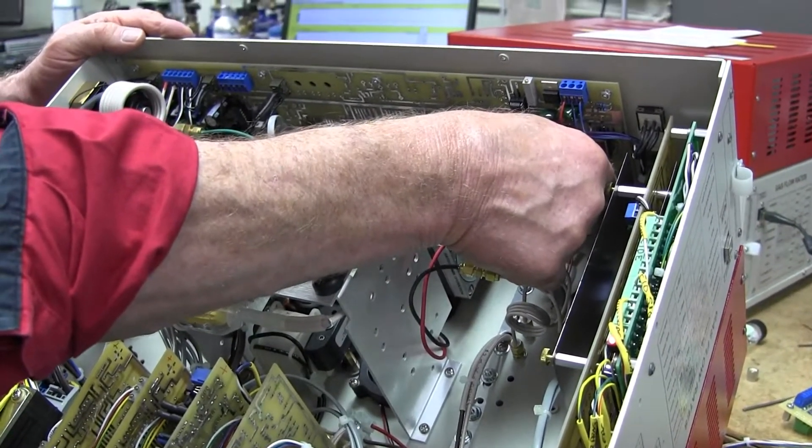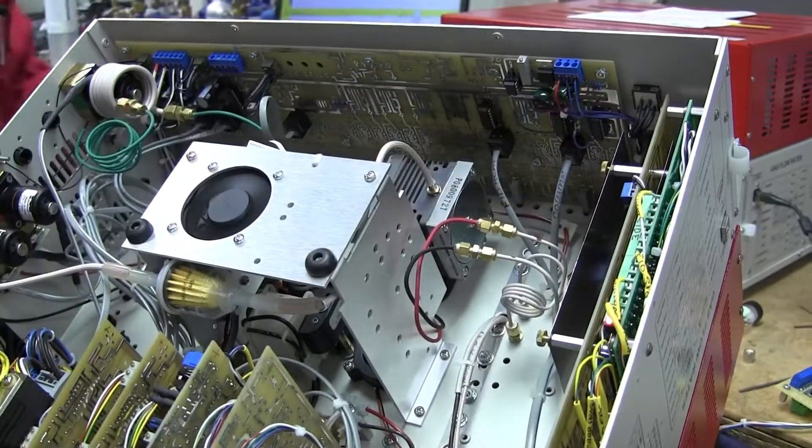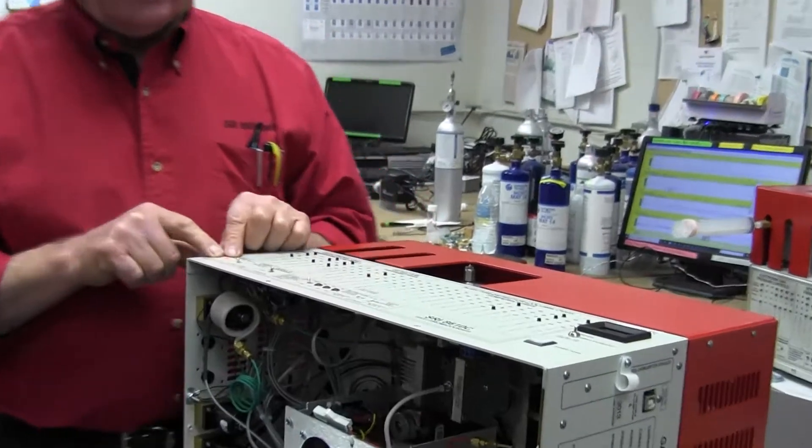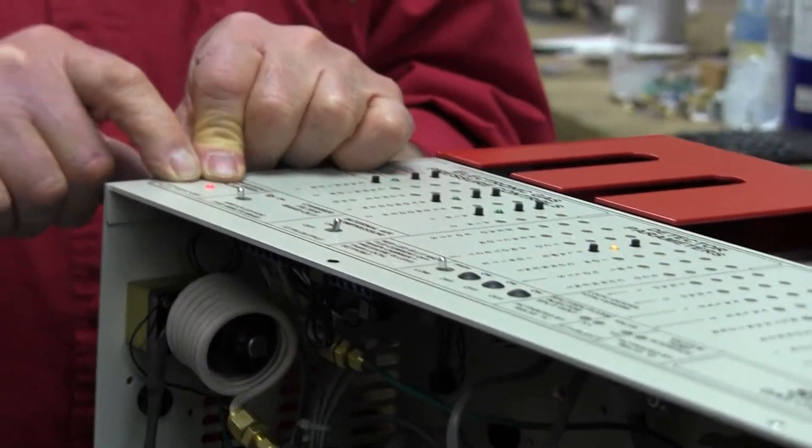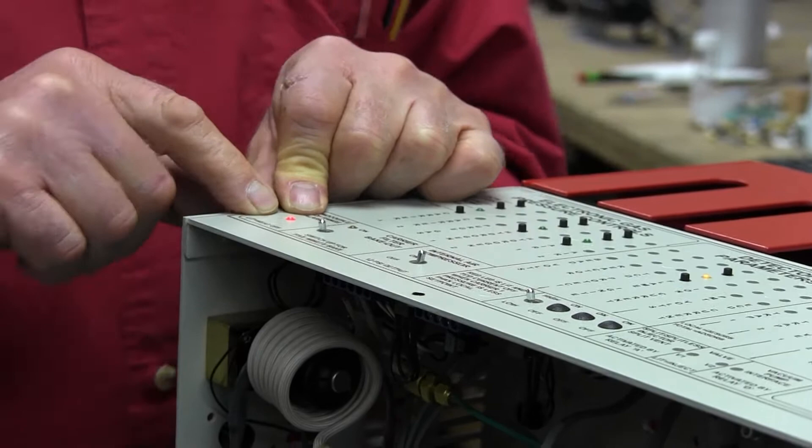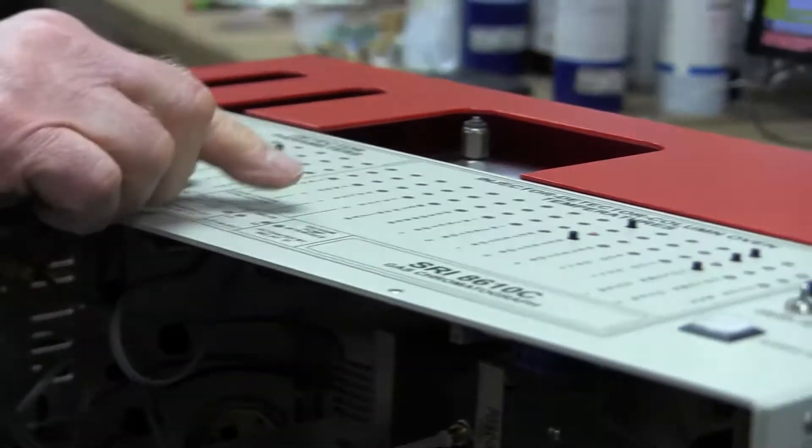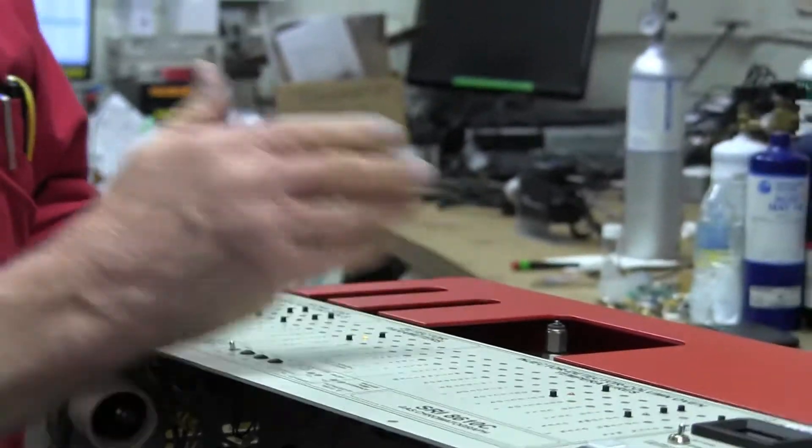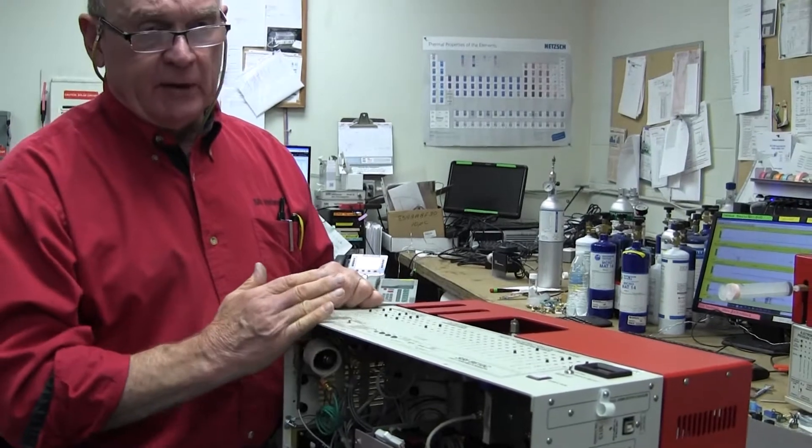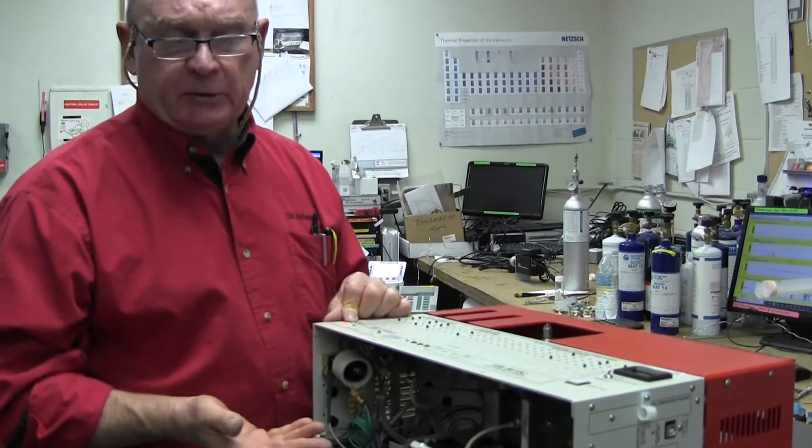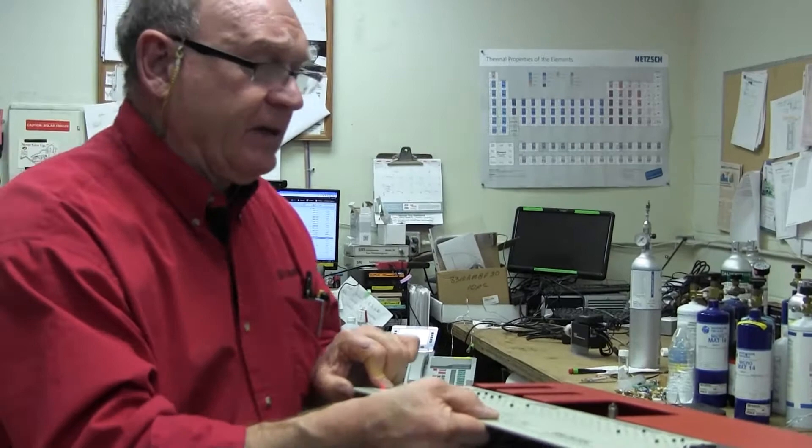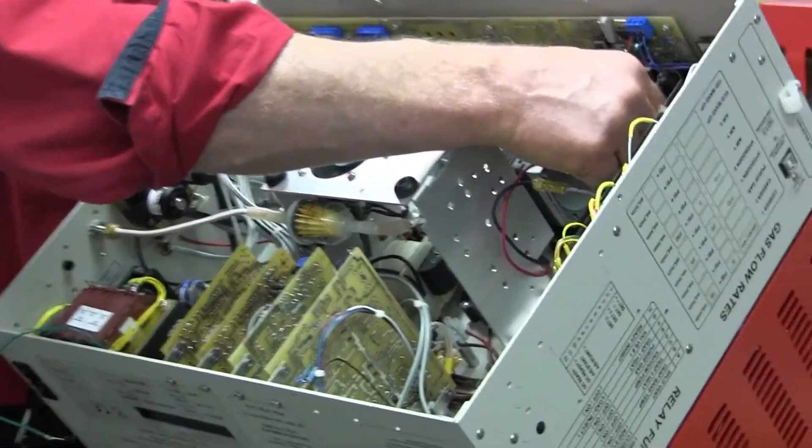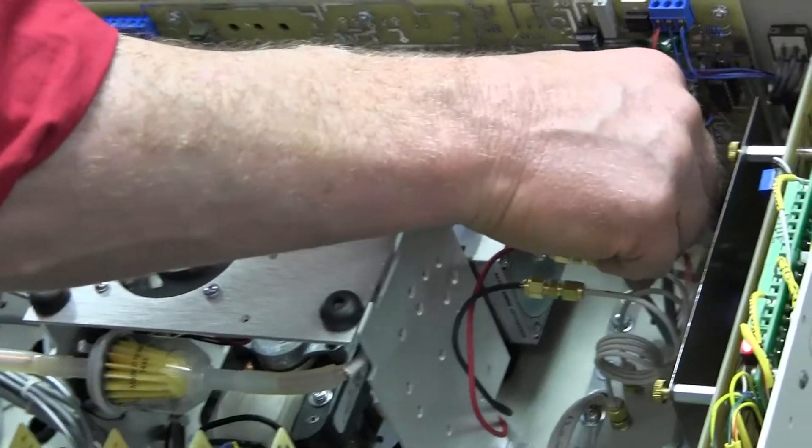if it's halfway out, then the thermocouple out-of-range alarm lights up, right? Because something's wrong. It's kind of a supervisory circuit that senses when the temperature of any of the things that heat is not somewhere between 5 degrees centigrade and 425 degrees centigrade. If it doesn't read somewhere in that range, then maybe the thermocouple is broken. Maybe there's something else wrong. But in any case, it's a safety feature that is important. So if something's unplugged, it's not going to heat, but it's also going to cause nothing to heat.